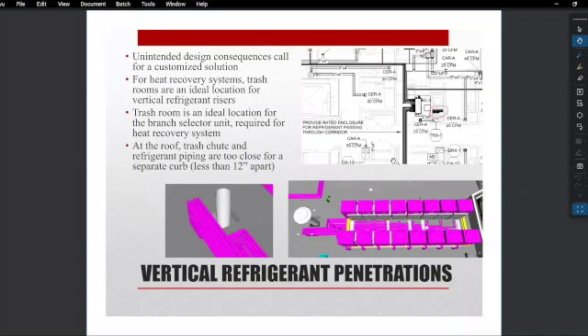For example, the trash chute is a really great place for the vertical risers to run up, and it's a great place to have the branch controller to do your distribution. But one of the problems is when it penetrates the roof, now the refrigerant risers are rather close to the trash chute. So it's not really feasible to do the prefabricated vault with the trash chute curb. In the picture we're showing here, those refrigerant pipes are about a foot away from the trash chute riser, so there's not enough room to build a curb around the trash chute and a curb around the refrigerant and do the flashing. It's just not feasible.